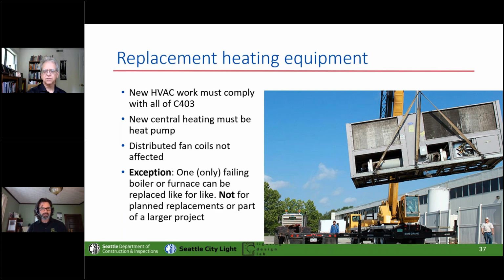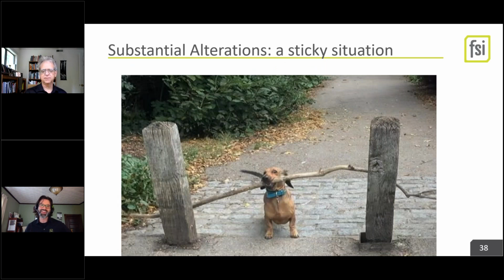Right. I was just thinking that when I made this rule, you've got to consider that there's design time, and when you put in a heat pump system to replace your old gas boiler, it'll take more physical space. You'll have to have an outside air source. You'll have to make new connections. So that's not just something you can sketch out in a couple of minutes and call up and order the parts for, right? Correct. Yes. It's a design project. And a boiler might just be a drop-in replacement if you can get your hands on one. Of course, getting your hands on anything right now is a trick.